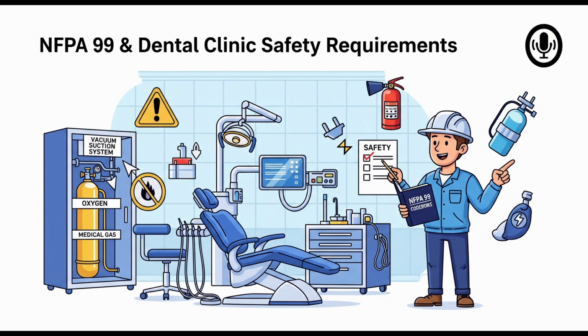Okay, what about ventilation for indoor storage? Ventilation is required, yes. It needs to comply with Chapter 9 of NFPA 99. If you use mechanical ventilation, an exhaust fan, there are specifics. The exhaust inlets should be near the floor, ideally within about a foot of the cylinders, because gases like nitrous oxide are heavier than air and can pool low. There are also minimum and maximum airflow rates depending on the room size. And ideally, the exhaust fan should be connected to the facility's essential electrical system if one exists, so ventilation continues even if the main power goes out. So even the ventilation is specified.